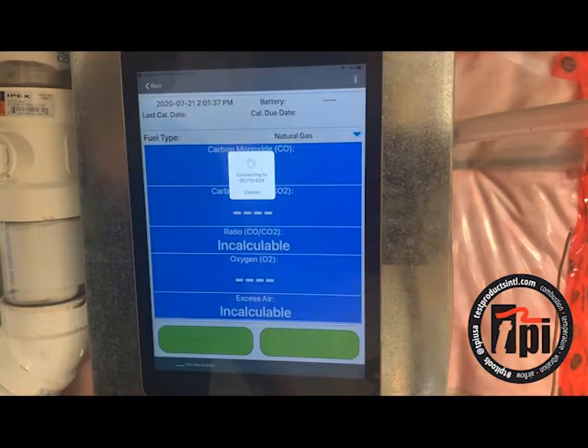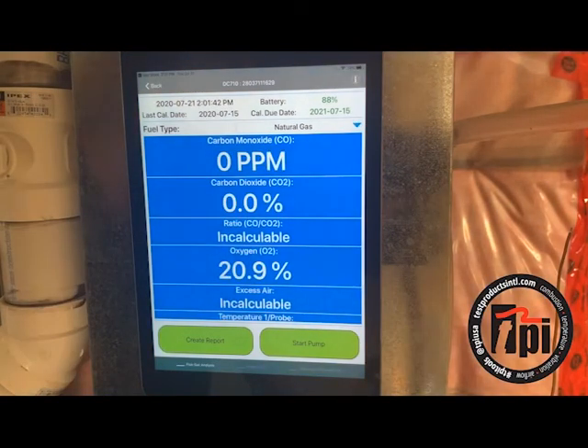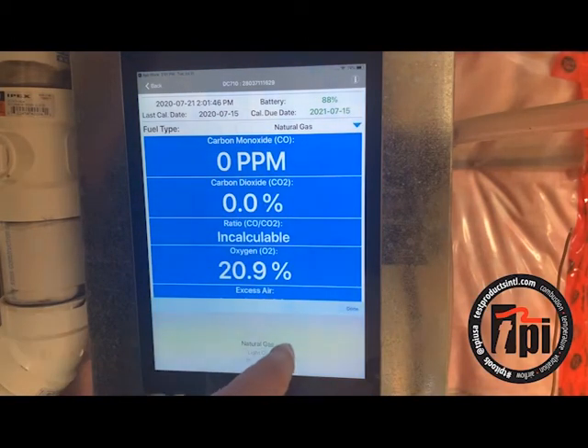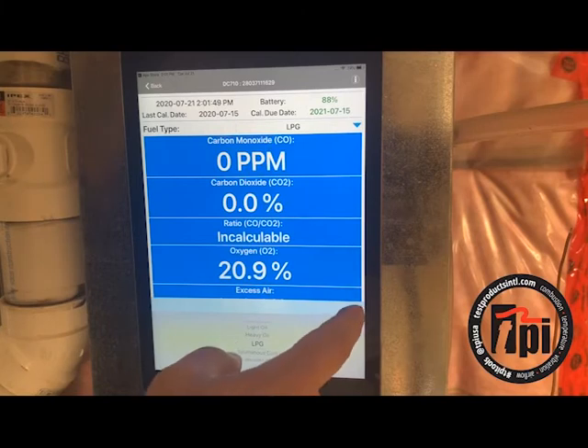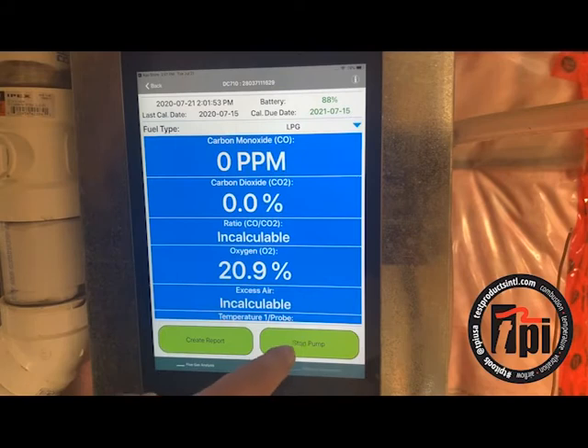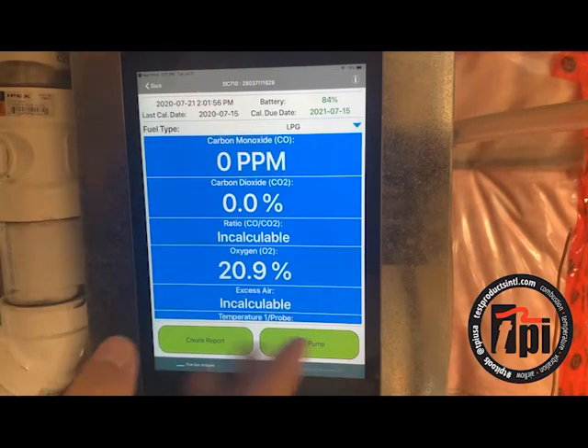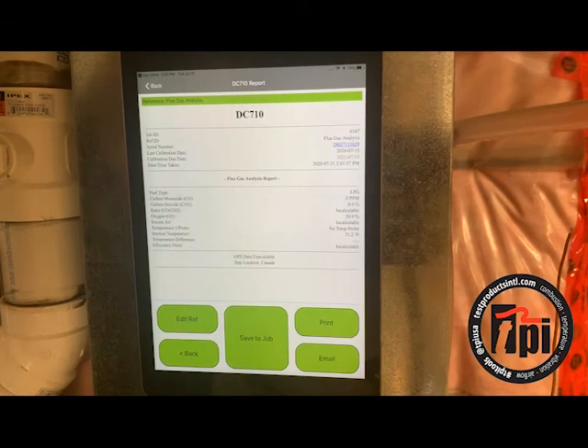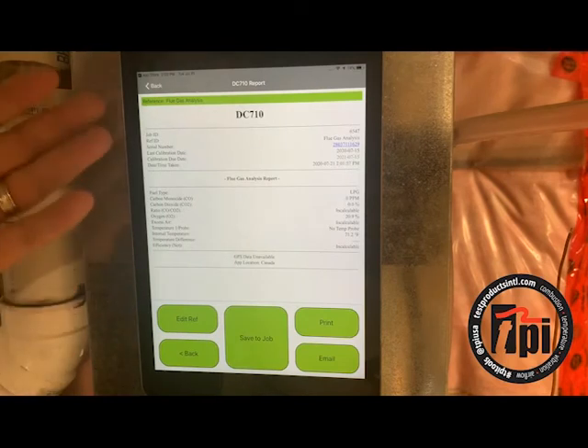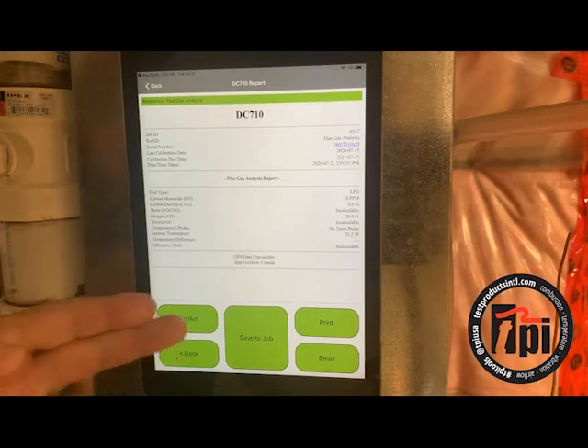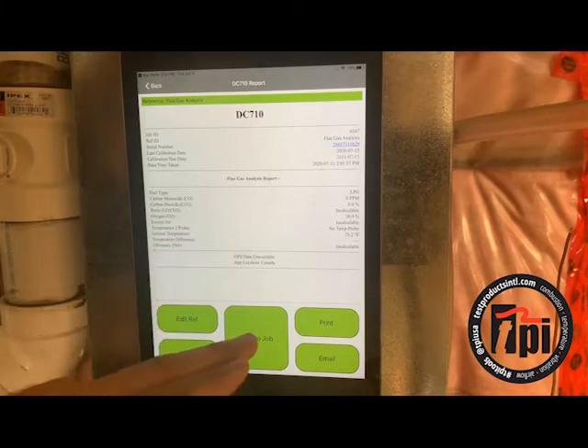Tap on that and there it is. From here, on my analyzer — I happen to be in front of a propane furnace right now — so I'm going to change it to LPG. I can start the pump and stop the pump remotely. As soon as my readings stabilize, I can create a report. So, flue gas analysis — let's just set that on there. It gives my time and date, and if I have satellite or cellular service, it will give me my GPS location, and I can save this to the job. I'm not actually doing live readings right now, just demonstrating the app.